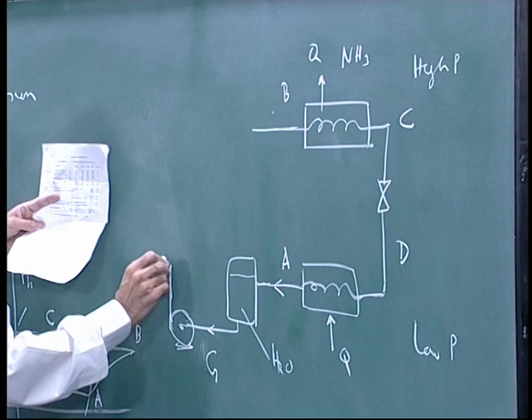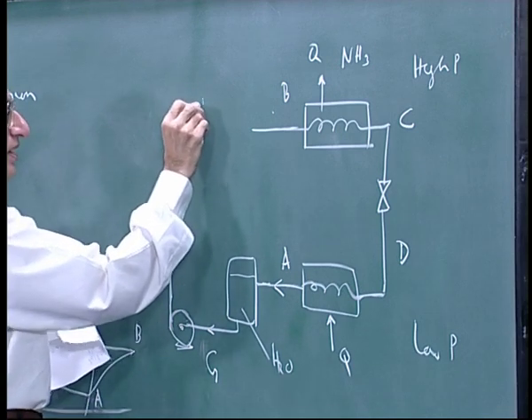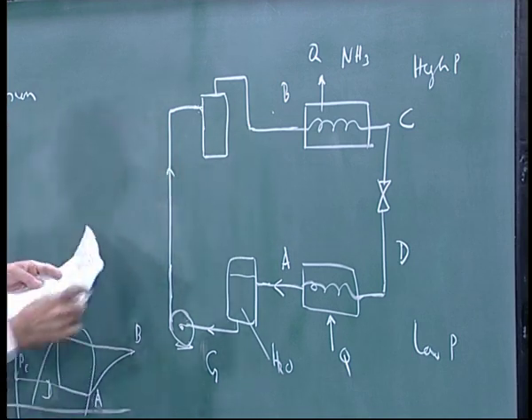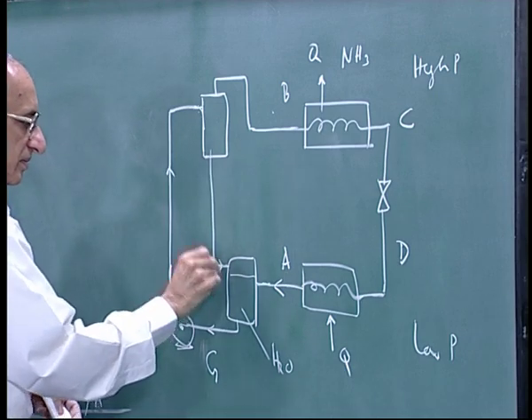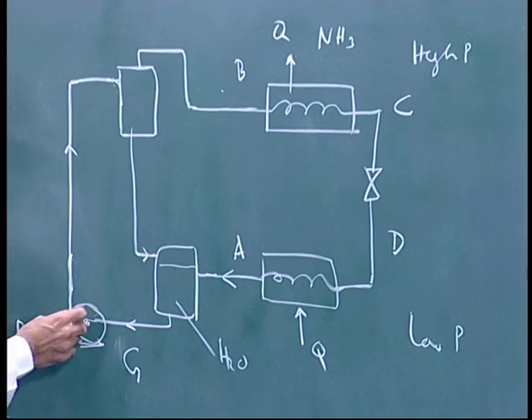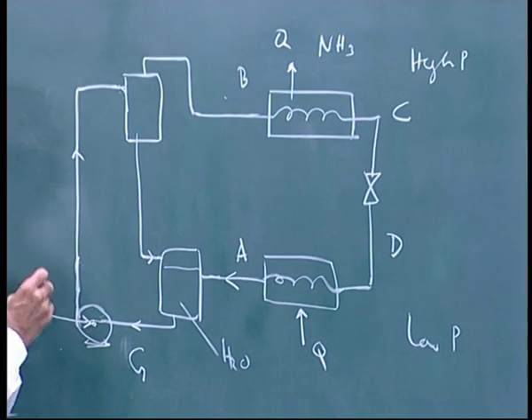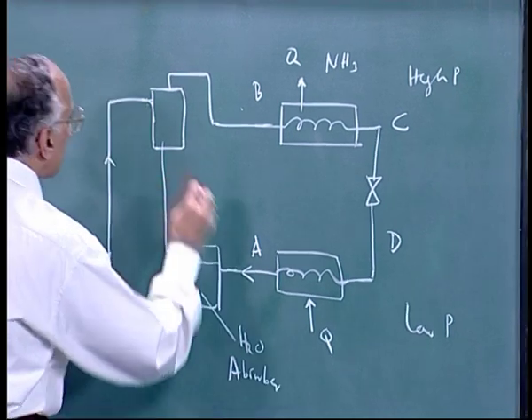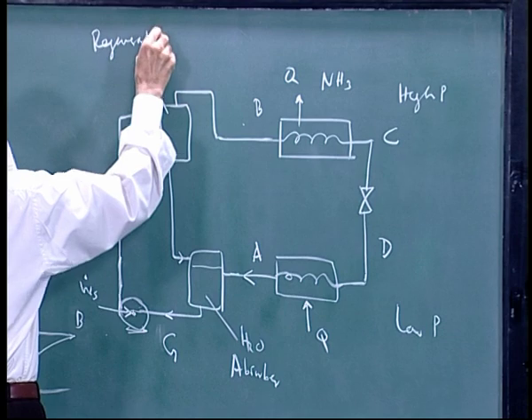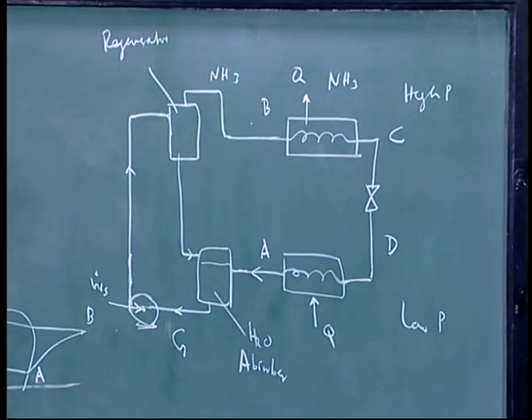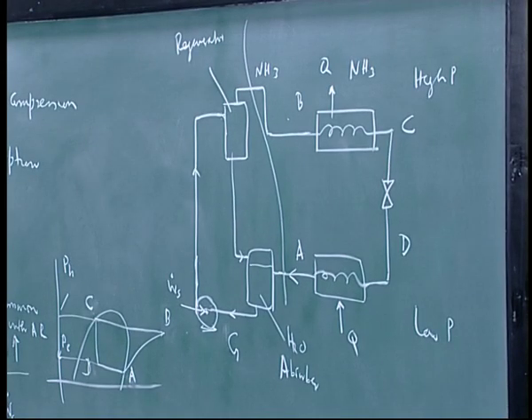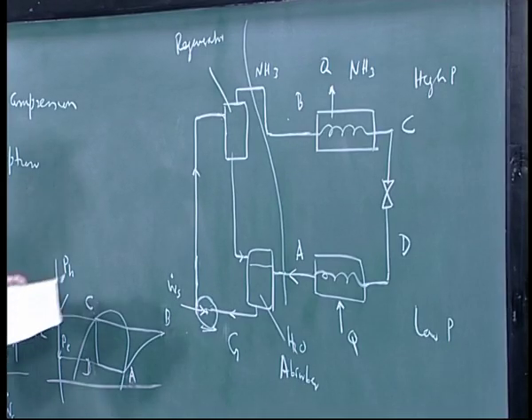From the regenerator the solution comes back down. I will put down some concentrations to describe the whole process. The absorber takes in ammonia vapor; the regenerator drives ammonia out, and what comes out of the regenerator is essentially pure ammonia with negligible amounts of water. The right-hand side of the cycle (condenser, throttle, evaporator) is the same as in vapor compression, except the refrigerant is ammonia instead of R-134A.